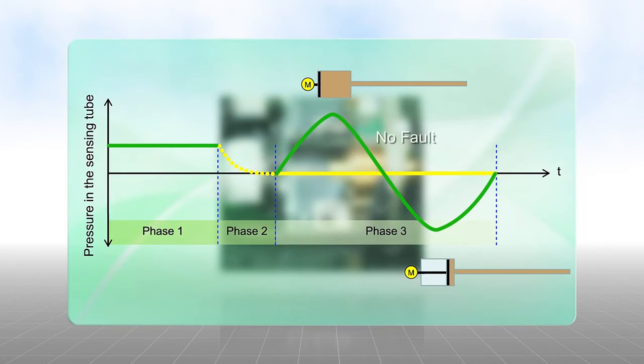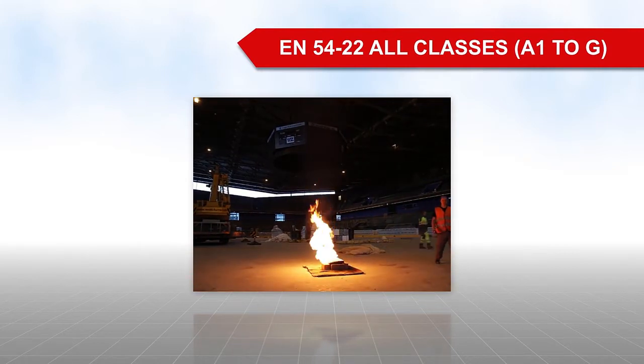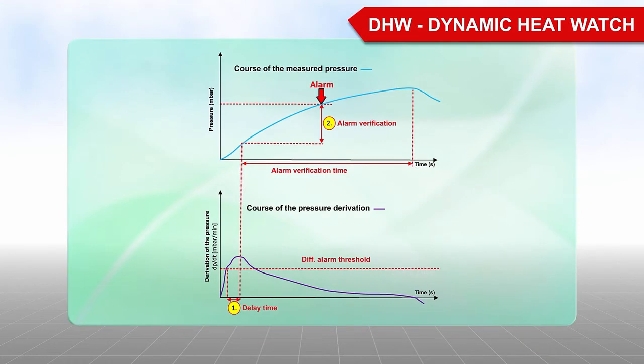If the measured pressure increase deviates from the saved nominal value, the computer reports a fault immediately. The response behavior can be set within a large range. The ADW535 is one of the quickest line-type heat detectors worldwide, and also complies with EN 54-22. The intelligent DHW dynamic heat watch algorithm on the ADW535 ensures that rapid increases in temperature caused by the ambient conditions do not result in a false alarm.